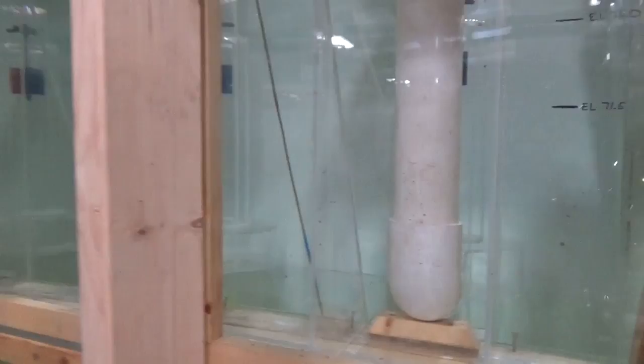I'll go up near a pump. We take a look at that. And we've got good flow going up into the pumps right here. Outside of it, it's turbulent, but there's a long draft tube that lets that flow stabilize before it gets up. Our velocity and turbulence have been in criteria all along.